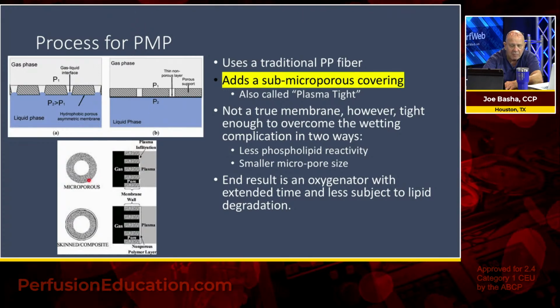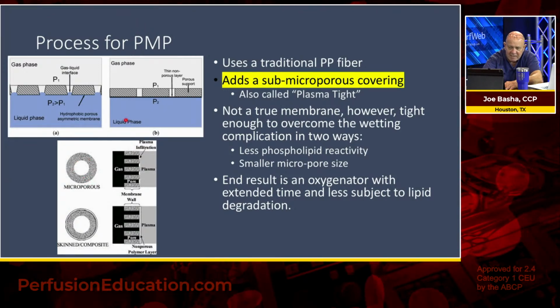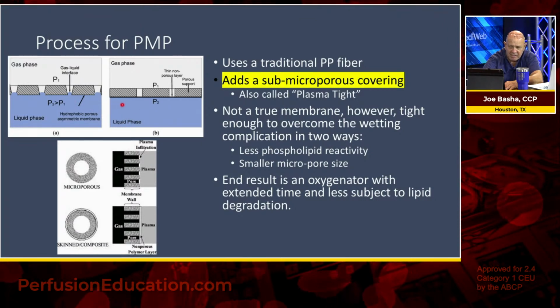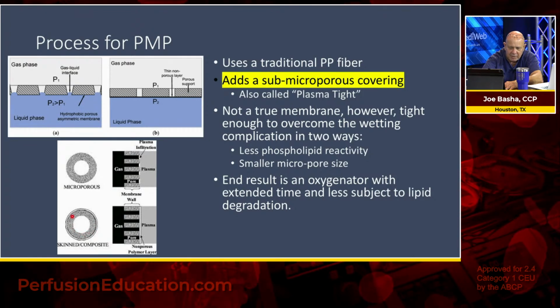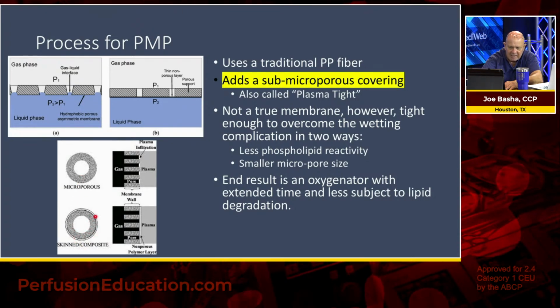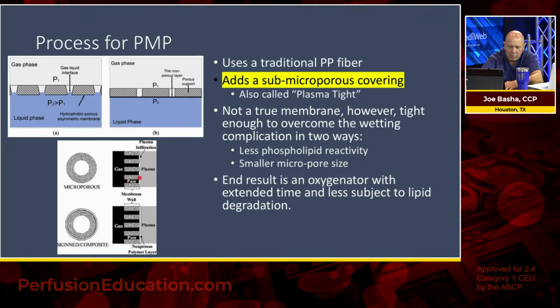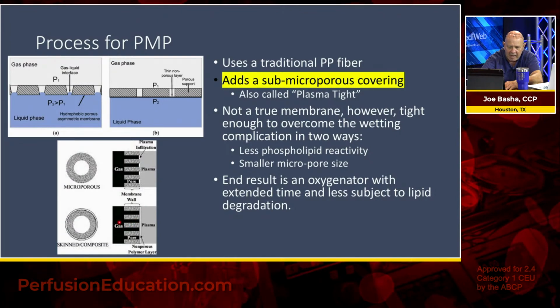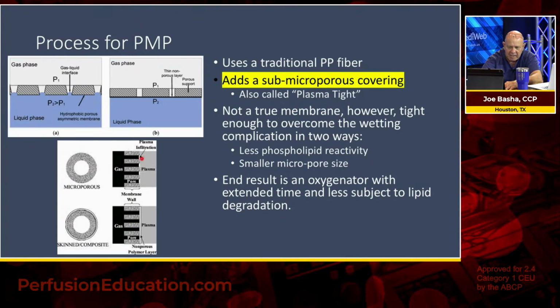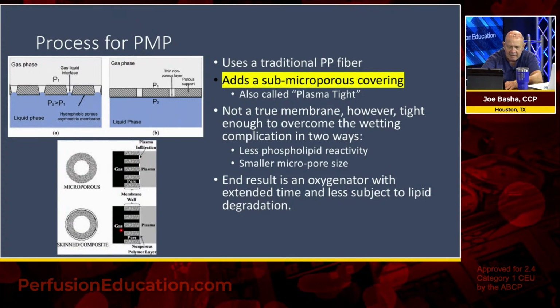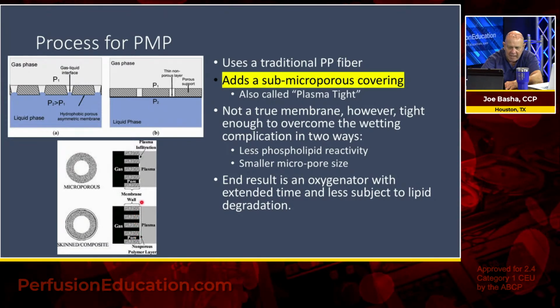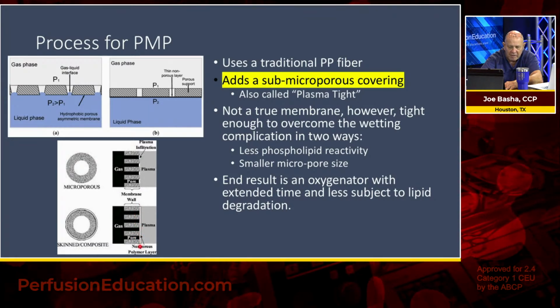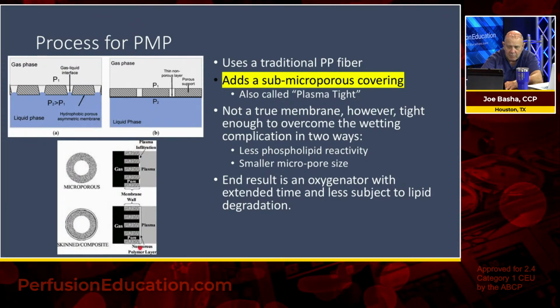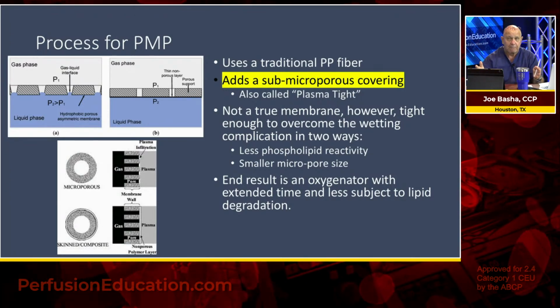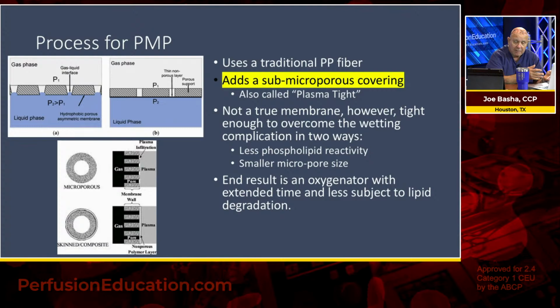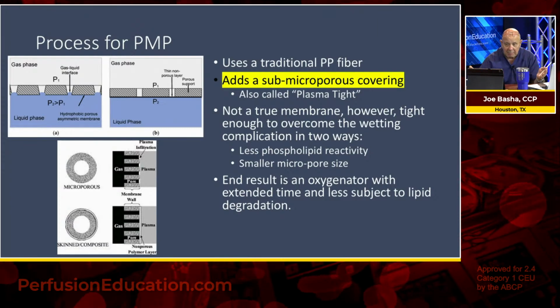And this is what it looks like cross-sectionally. Here's microporous, and again, this is made from the exact same materials. It's just that you have this skin that you see here. So here is the microporous without a skin. Here it is with a skin. Same representation: gas, micropores, plasma, and here you have plasma infiltration actually being demonstrated. And you have gas, you have plasma, you have your pores, but you have this submicroporous polymer layer, or skin, if you will. And that's the difference between polypropylene oxygenators and polymethylpentene oxygenators, summed up in that one slide.